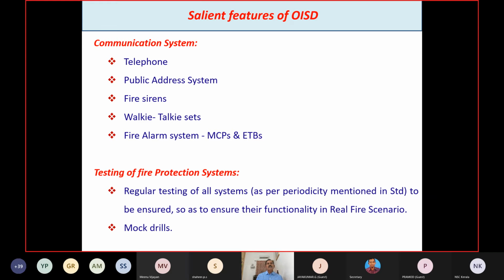The emergency trip buttons: if you operate the emergency shutdown button, you will get an alarm in the control room and a siren will be started, and the power supply to all prime movers will be cut off, and all ROVs of the tanks will be closed on their own. So this system should also be available.